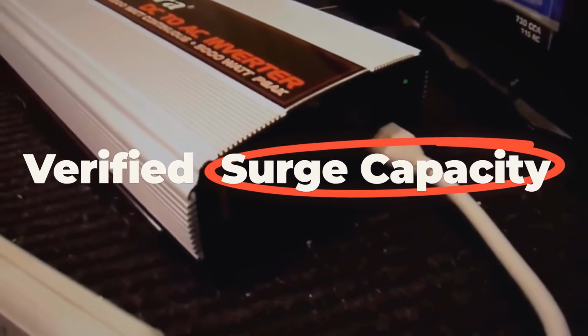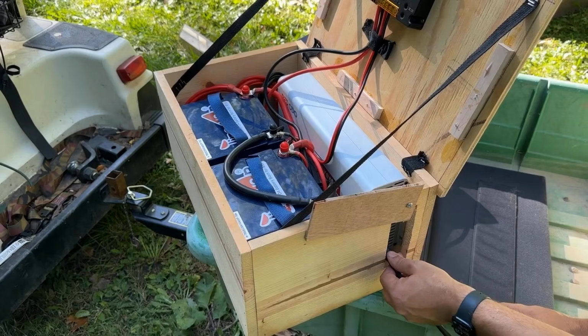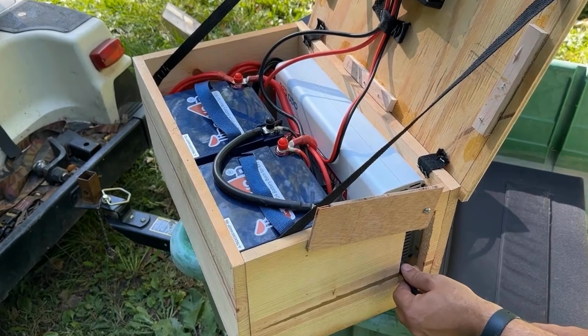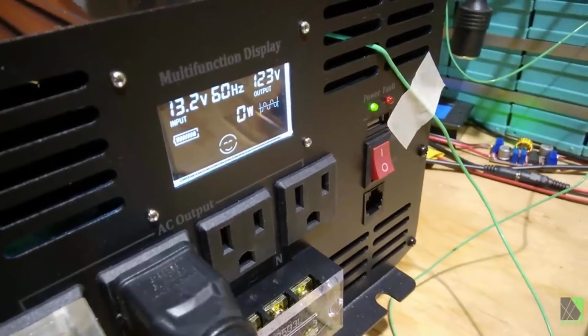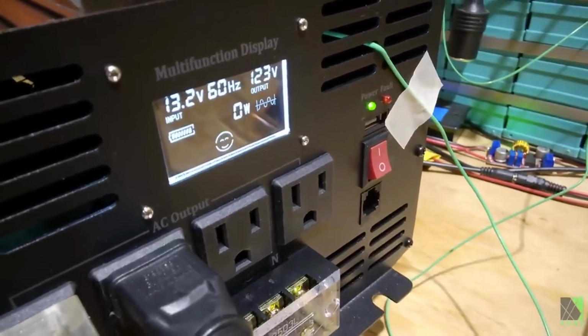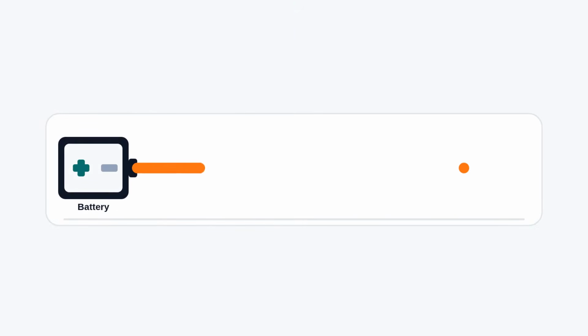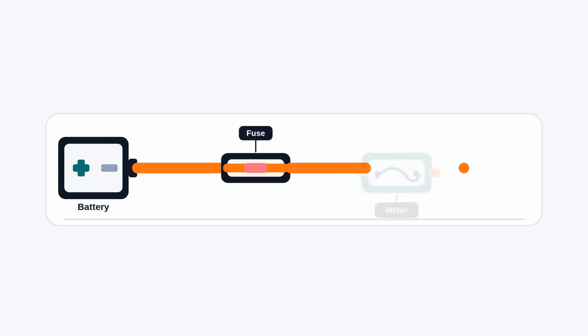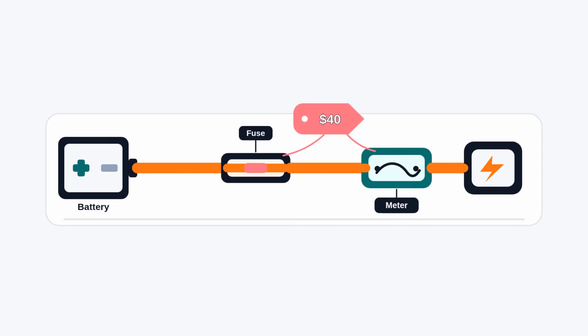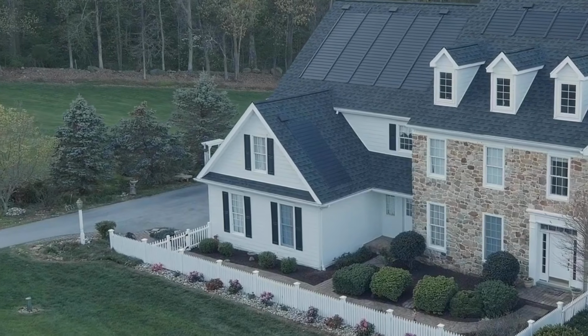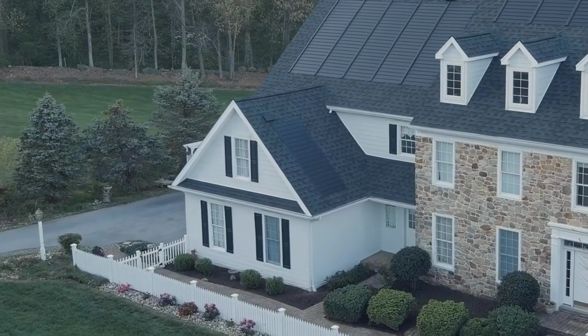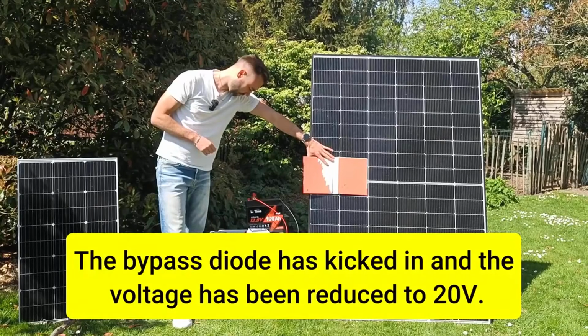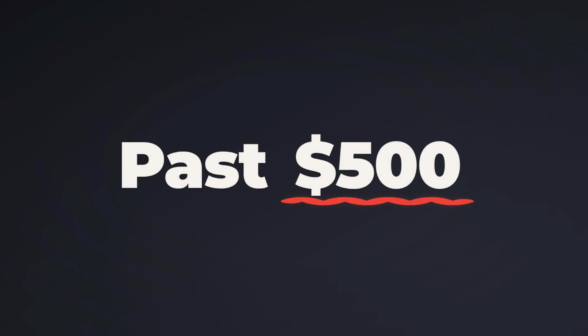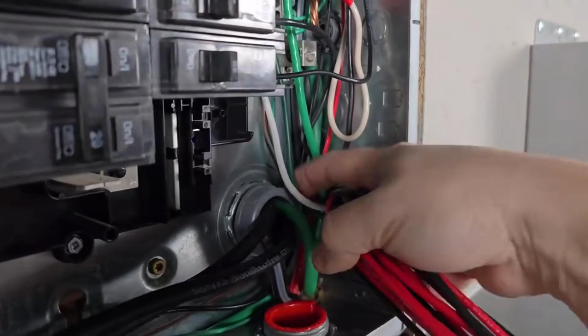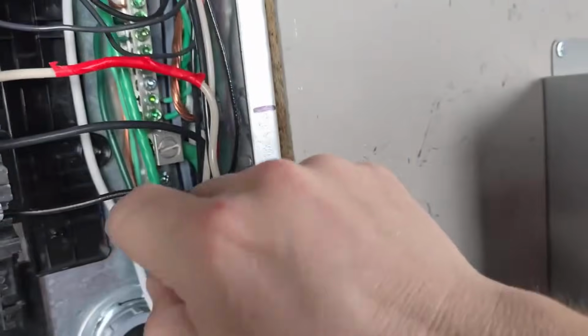The inverter needs verified surge capacity to start a compressor, which means a tested 1,500 watt unit minimum, not a 1,000 watt unit with a 2,000 watt sticker. That is another $80. Properly gauged copper cable, rated fuse holders, and a basic inline meter to confirm real performance add 40 more. Then panels sized for your actual daily harvest, accounting for tilt, shade, and realistic irradiance hours, not the peak figure on the box. Price all of it together and you are well past $500 before installation or any transfer switching that safely isolates your backup load from the grid.